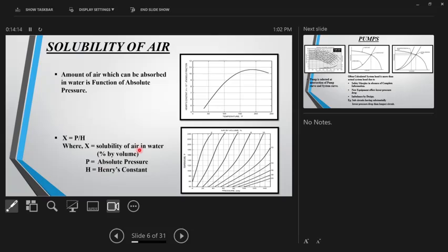What it means is if the air is actually soluble in water, you may not be able to remove it. You can remove the air which is only separated out from water. So that's the reason why if you try to separate the air from the basement, you would not be able to do that very efficiently, correct? Because at that location the pressure is maximum, hence solubility of air is maximum, hence you can't remove the air. So usually, if you see, the air removing devices are at the topmost point. Again, the basis of that is this equation, that at the topmost point the pressure is less, solubility is less, so more air is actually available for you to bring out of the system. So this equation gives how much, at what elevation, what opportunity you have to remove the air.